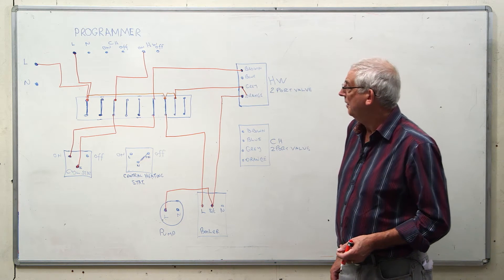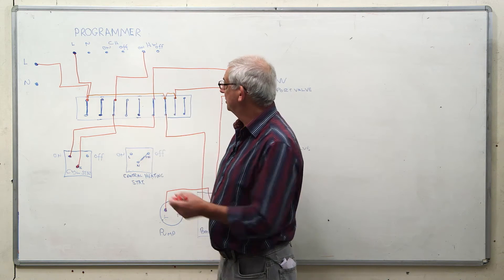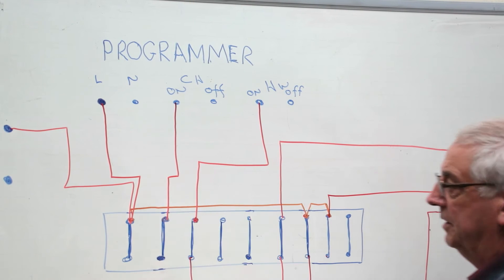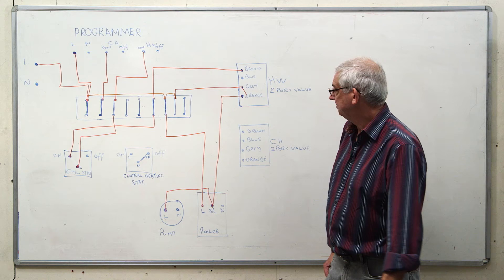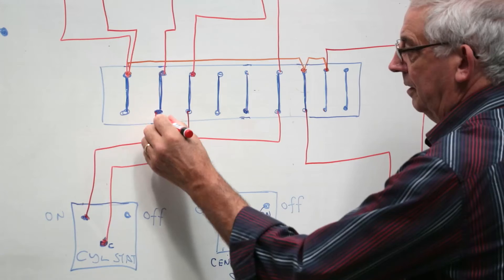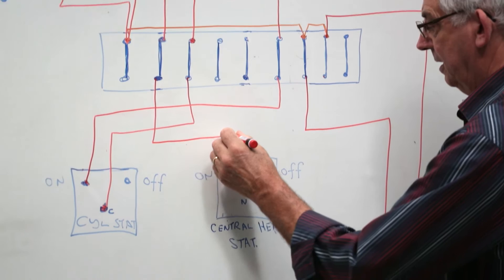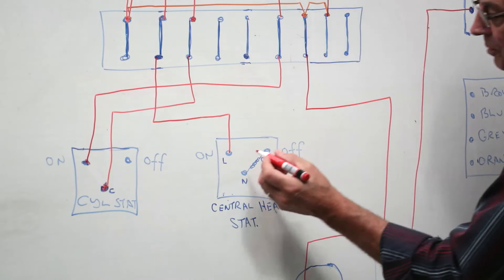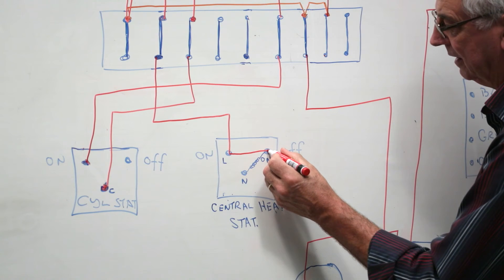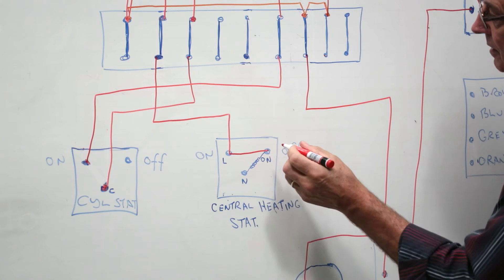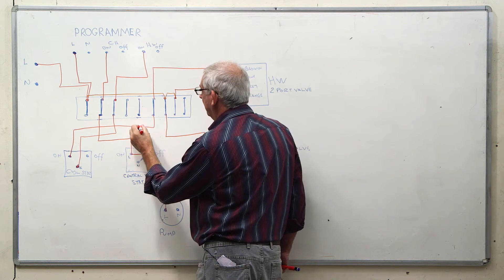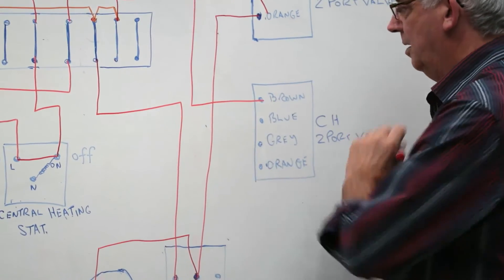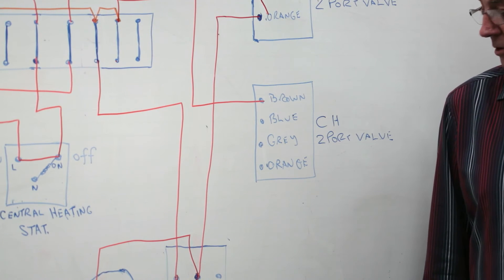If we look at the central heating now, central heating is called for, so I send a signal to my wiring centre, from the wiring centre to the common of my thermostat. Thermostat's calling for heat, sends a signal back up to my central heating two port valve.